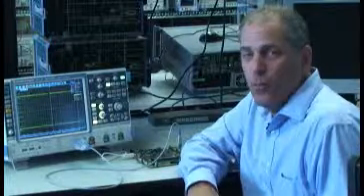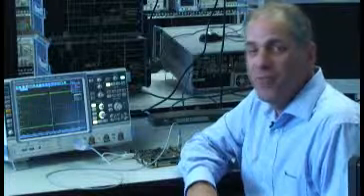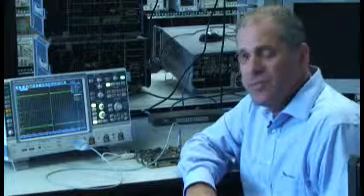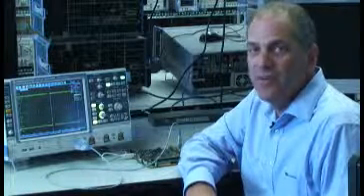Here we're going to take a look at waveform update rate. Waveform update rate in digital oscilloscopes has been a hot topic lately. Many manufacturers specify extremely high update rates in excess of 1 million waveforms per second.